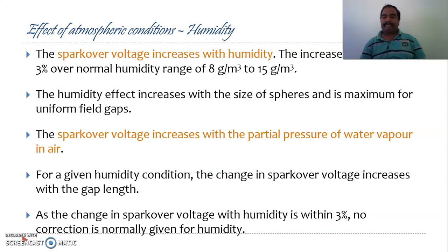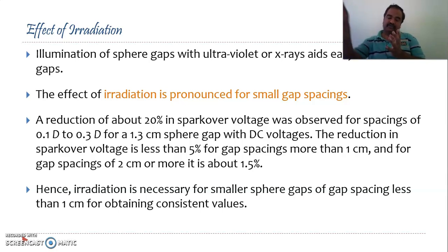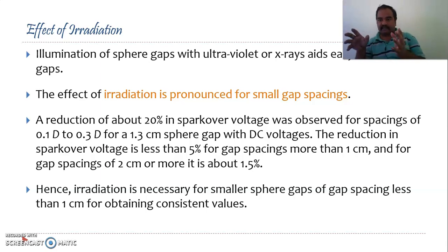The humidity factor alpha: it has been observed that spark-over voltage increases with humidity. Whenever the partial pressure of water vapor increases, the spark-over voltage also increases. The other factor is irradiation. As seen in ionization chambers, a radiation source creates electrons. So if small gap spacings are used and any radiation is present near them, it will aid ionization and ignite your gap. The first point says illumination of sphere gaps with UV or X-rays aids easy ionization in gaps. Make sure there are no sources of radiation near your measuring chambers.